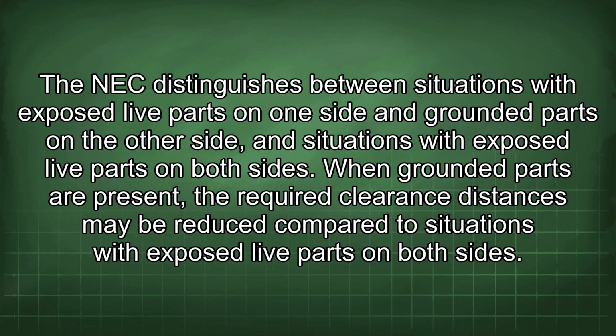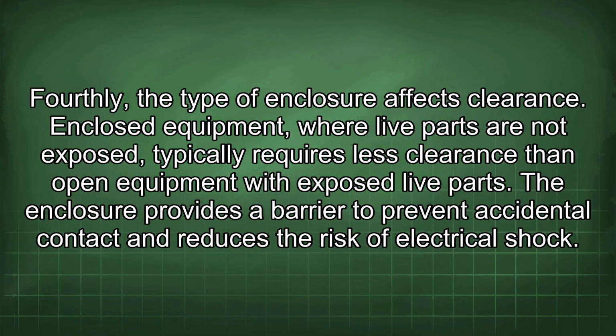The NEC distinguishes between situations with exposed live parts on one side and grounded parts on the other side, and situations with exposed live parts on both sides. When grounded parts are present, the required clearance distances may be reduced compared to situations with exposed live parts on both sides. Fourthly, the type of enclosure affects clearance. Enclosed equipment, where live parts are not exposed, typically requires less clearance than open equipment with exposed live parts. The enclosure provides a barrier to prevent accidental contact and reduces the risk of electrical shock.